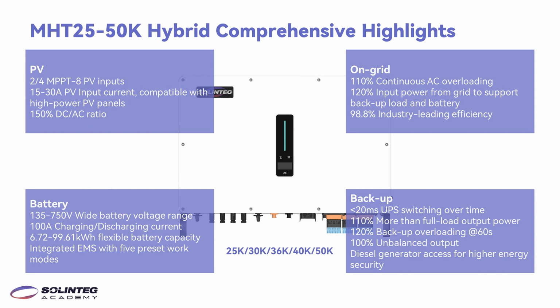And for DC and AC ratio, it is 150%. That means you can connect more PV panels on PV side. So more PV power can come into inverter to support the loads and charge the battery at the same time.